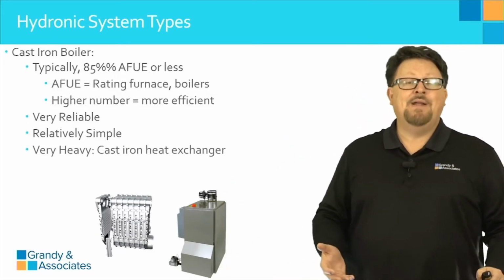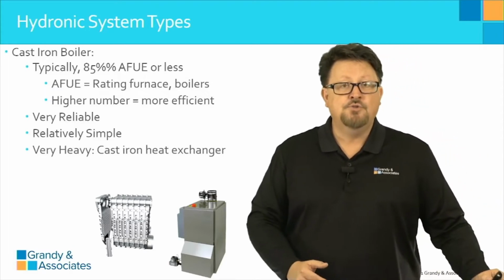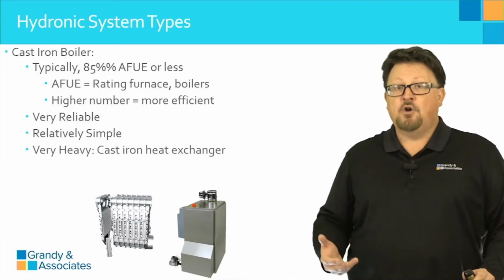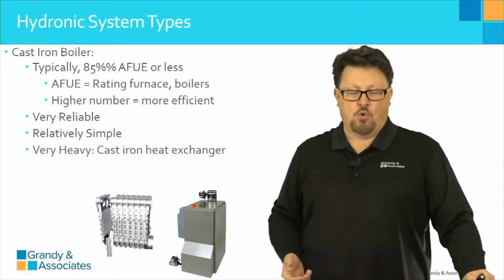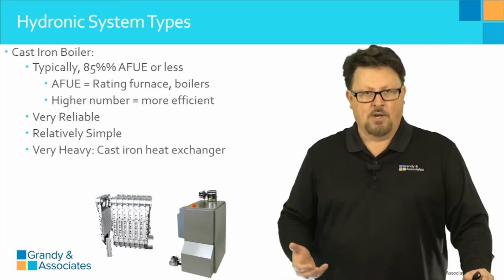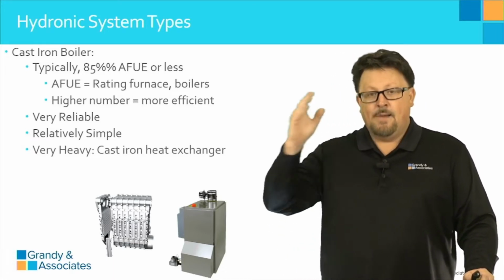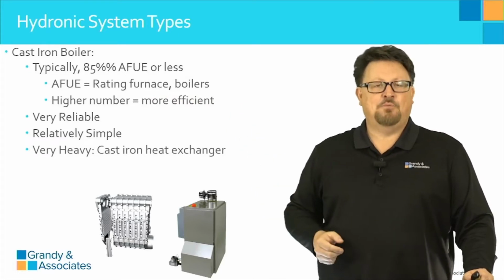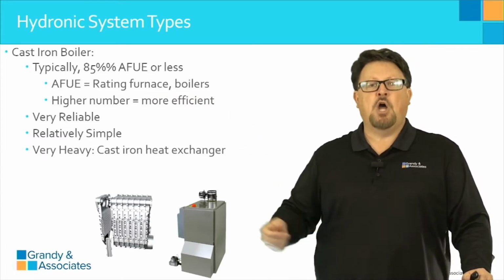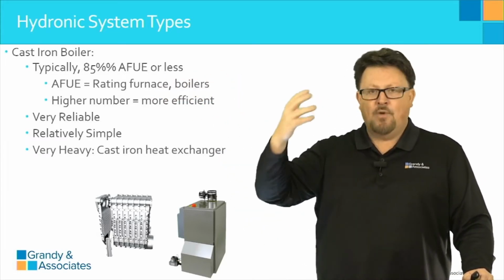There are two primary designs of boilers used within the industry. The first is kind of the classic workhorse, the cast iron boiler. These are rated 83 to 85% efficient on something called the AFUE rating or scale.